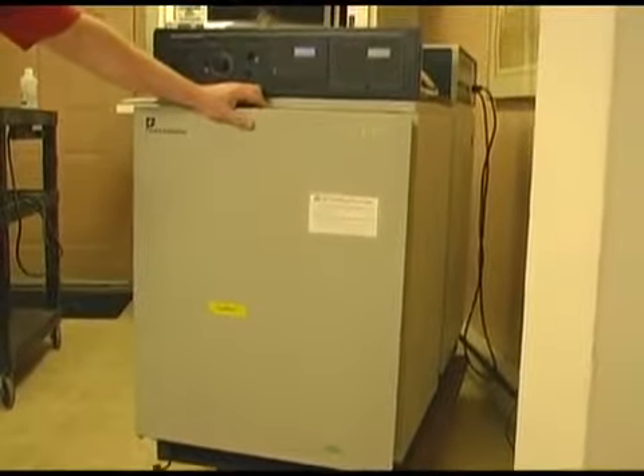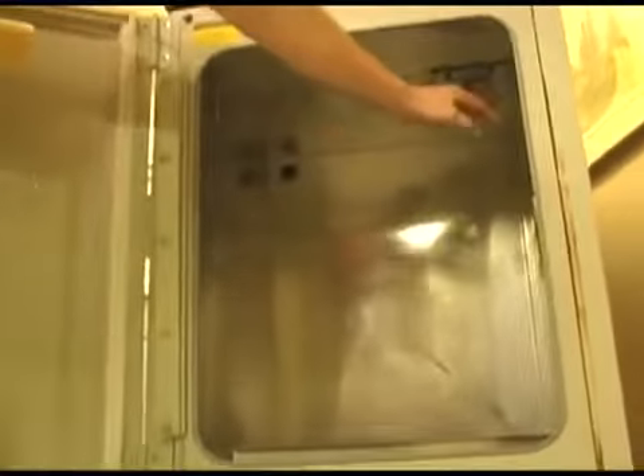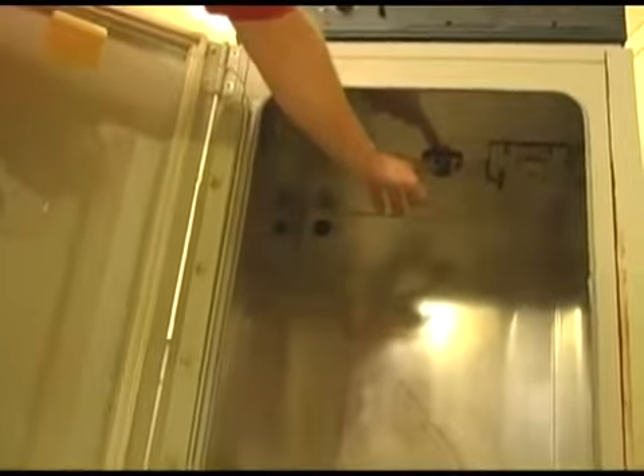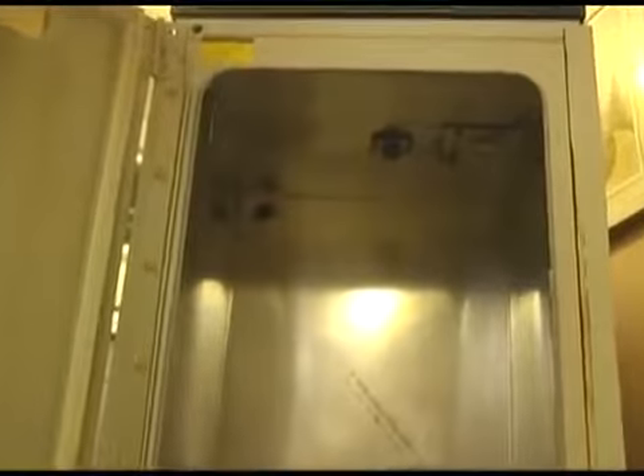The chamber usually has an outer door and an inner door. Most chambers that I've seen are all stainless steel. Inside the chamber of this particular unit, you can see a fan which maintains the CO2 in the chamber to the same level throughout it, and a CO2 detector. There's generally two types of detector. One is thermal and one is infrared. The thermal is what you're viewing here. If it was an infrared, you would see two LEDs, and by the way, that's an indicator that basically the CO2 sensor is working for the infrared.